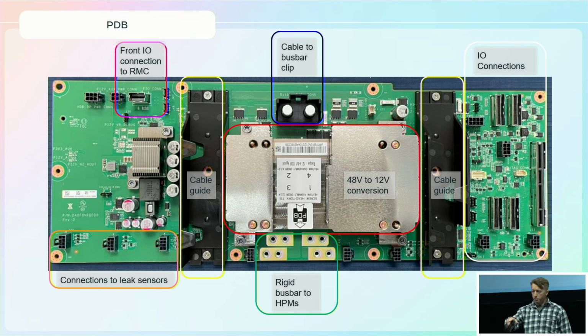If we start at the blue box toward the top middle, that's the cable getting you from the bus bar clip to the PDB, carrying the 48 volts. It travels on this flexible, thick cable and plugs in. The PDB's main job is to distribute power throughout the tray. It takes the 48 volts and makes it 12, which is our primary distributed voltage within the tray, fed to the HPMs, the fans, and everything else.